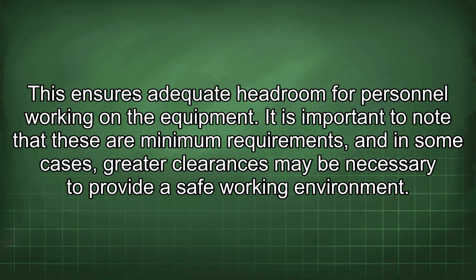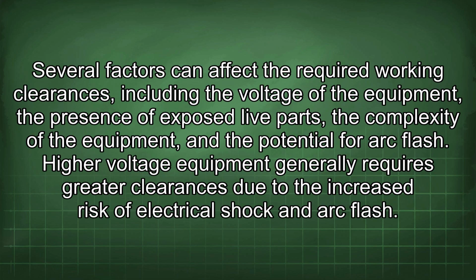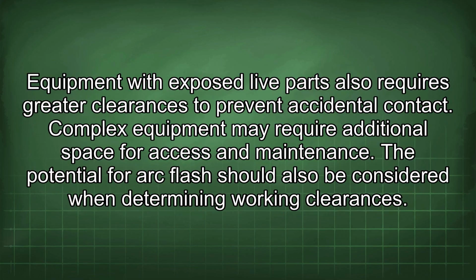It is important to note that these are minimum requirements, and in some cases greater clearances may be necessary to provide a safe working environment. Several factors can affect the required working clearances, including the voltage of the equipment, the presence of exposed live parts, the complexity of the equipment, and the potential for arc flash. Higher voltage equipment generally requires greater clearances due to the increased risk of electrical shock and arc flash. Equipment with exposed live parts also requires greater clearances to prevent accidental contact. Complex equipment may require additional space for access and maintenance.